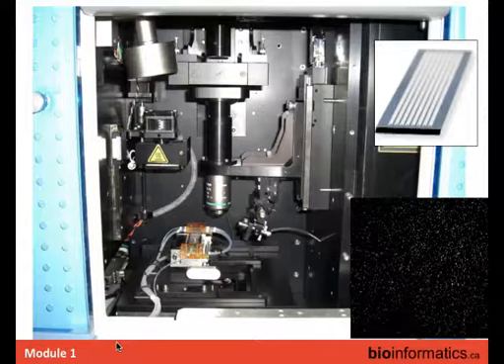Inside one of the early Illumina instruments — you can tell it's Illumina because it's blue — it's really just a microscope slide with eight channels, a couple of holes at each end to pump reagents through. The instrument itself is essentially a microscope with an objective, robotics to move it, and liquid handling to add reagents. These older-style flow cells are being passed around so you can see them.